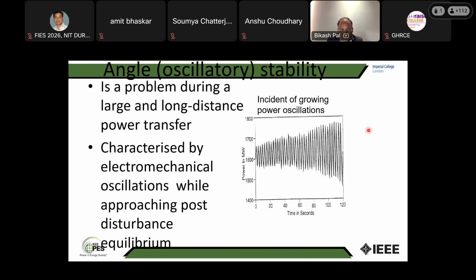This is sometimes called inter-area mode. If the oscillation is within the power plant complex, then that is called intra-plant mode. If the oscillation is between the generator itself and the rest of the network, then that is called local mode. But we are not going into the local mode or intra-plant mode because that is within the power plant complex. Let's go into the inter-area mode because we are talking about long distance transmission. So what are inter-area oscillations? Generators in one power plant, when there is a small disturbance or change in the power flow, would have electromechanical oscillation, and they would oscillate against the generators in other locations.